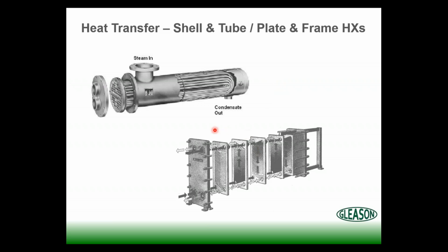And so the plate and frame unit here, some advantages there. They typically cost less. They take up less space. We can do a lot more heat transfer in a smaller footprint. So they both have their pluses and minuses. They do cost a little bit less, but some people don't like it because they have gaskets between each plate, and those gaskets can leak. And so they get tired of that sometimes if they're not maintained properly.